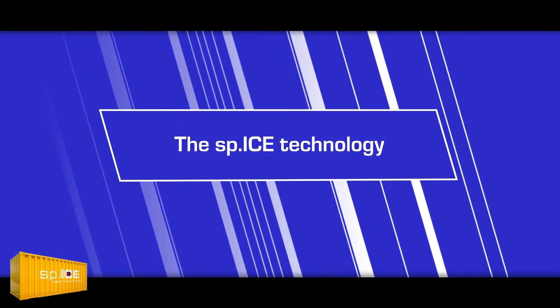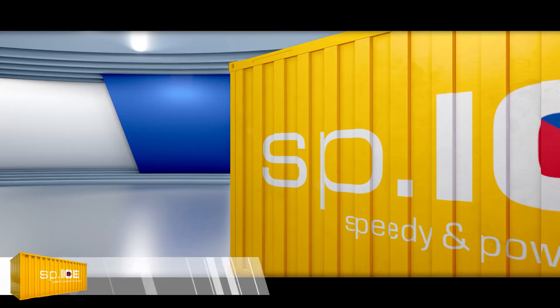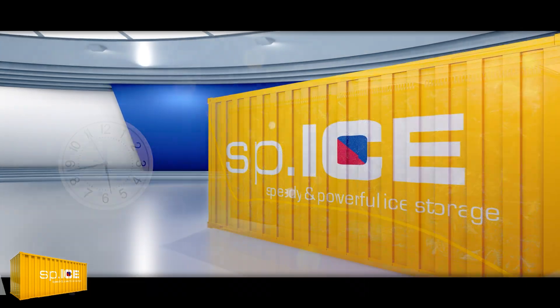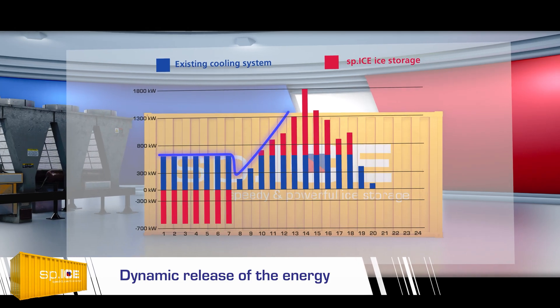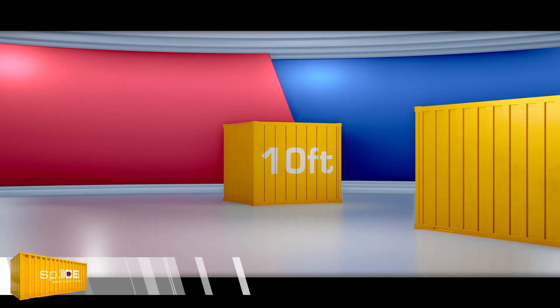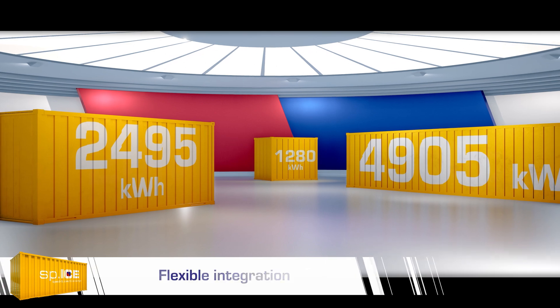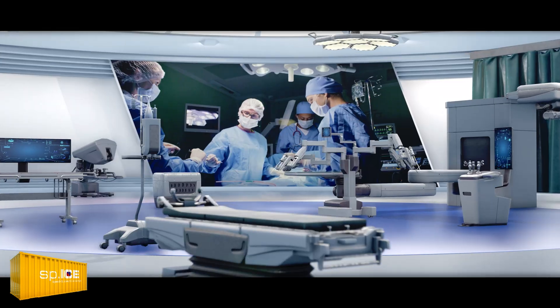The SPICE technology. Our innovative and patented technology, comprising capillary tubes in an efficient arrangement, is able to fully charge the SPICE storage bank in only six hours. When discharging, it is very dynamic and perfectly suited to covering peak loads. The SPICE is of modular construction and combines high-end cooling capacity with flexible options for installation and integration into existing air conditioning systems. Now we are going to present four key areas of application.